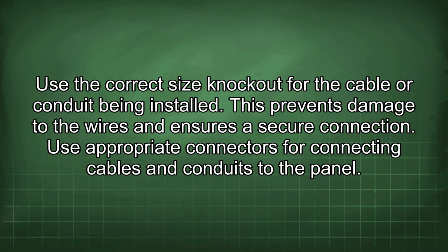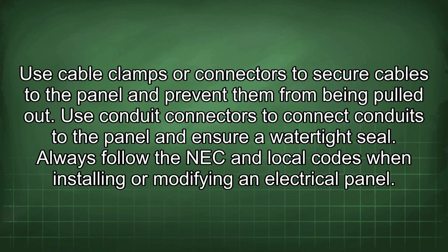Use appropriate connectors for connecting cables and conduits to the panel. Use cable clamps or connectors to secure cables to the panel and prevent them from being pulled out. Use conduit connectors to connect conduits to the panel and ensure a watertight seal.